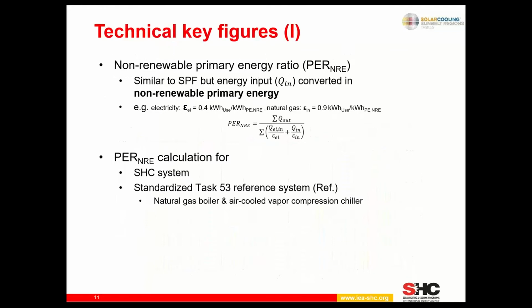On technical key figures, we are calculating in this tool the non-renewable primary energy ratio, PER NRE. It's similar to an EER or SPF: we calculate useful energy and divide it by needed auxiliaries. But in our case, we don't divide by electricity or thermal input values, we divide by non-renewable primary energy. So we convert electricity or any other input into non-renewable primary energy equivalents and calculate this PER. Of course this PER is in a completely different range than comparable EERs or SEERs, seasonal energy efficiency ratios, so we need to take care not to confuse our stakeholders, or ourselves.